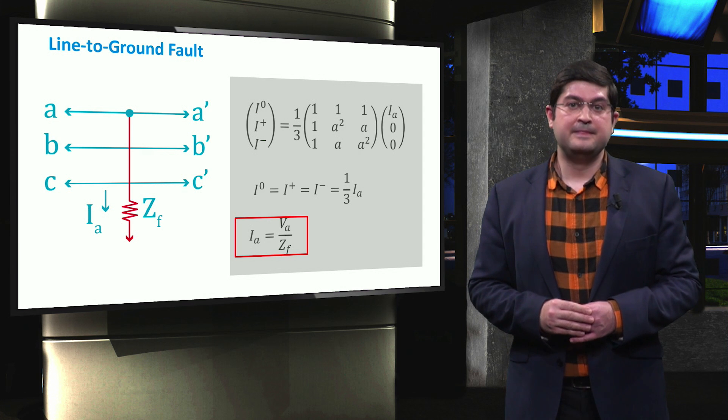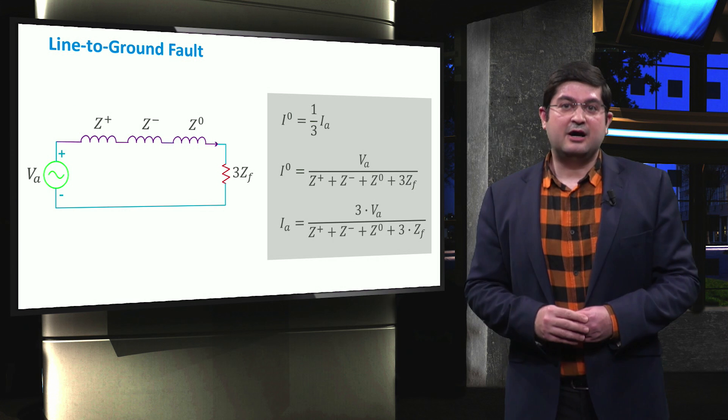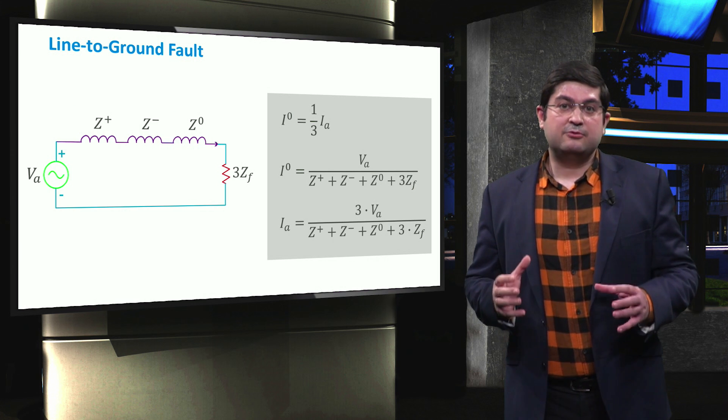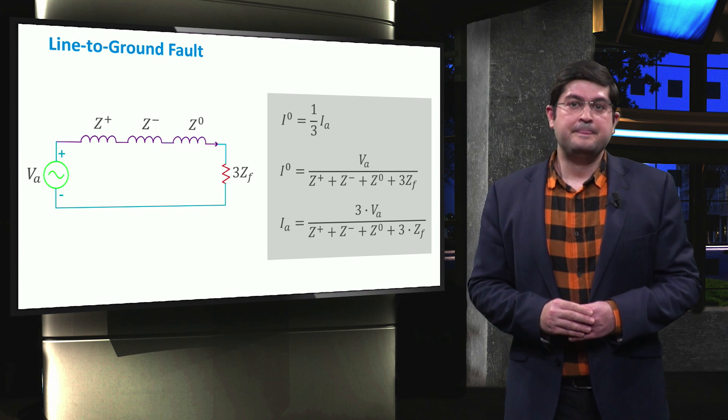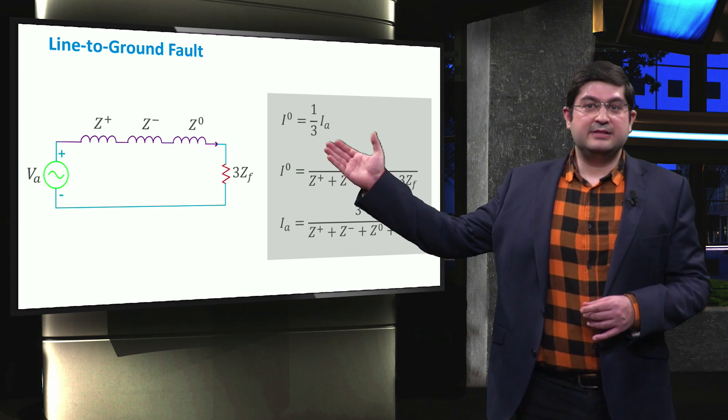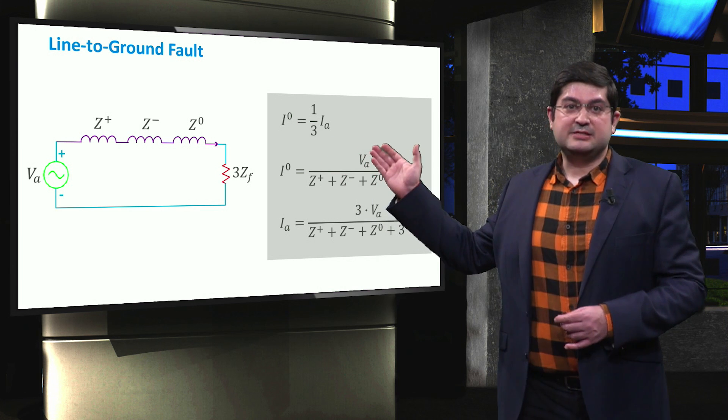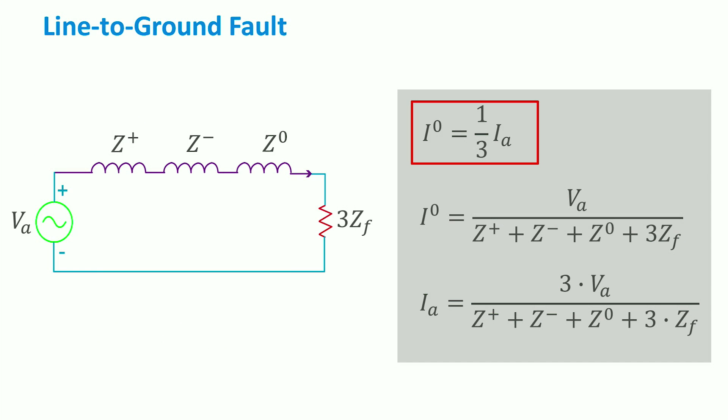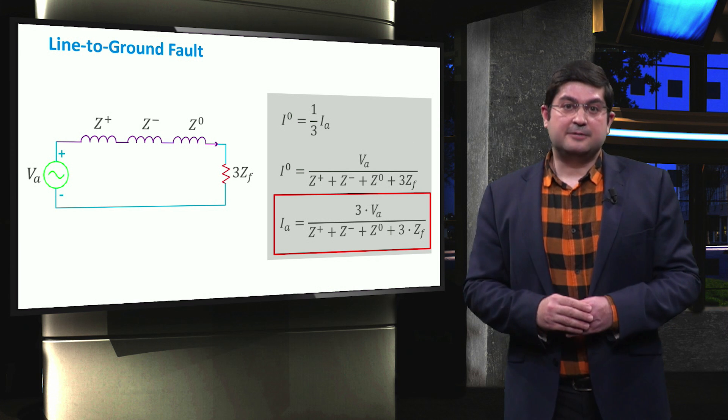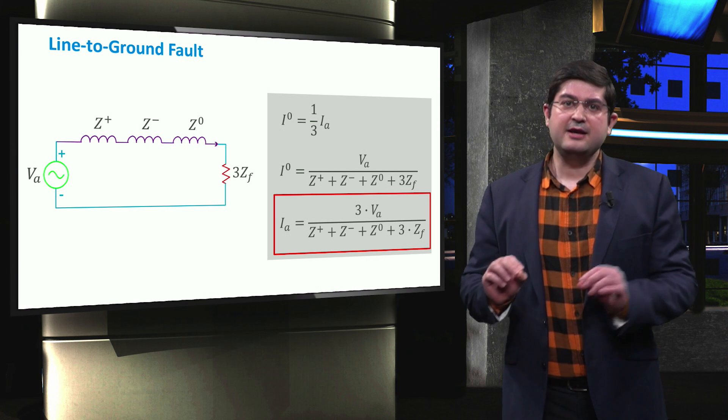In this slide, we show how the inclusion of the line impedance makes the previous calculation more accurate for a line-to-ground fault. We represent the impedances by the positive sequence impedance, negative sequence impedance, and the zero sequence impedance. As we have obtained, the zero sequence current equal to one-third of the fault current in the equivalent circuit, the three times ZF appears. The zero sequence current can then be obtained dividing the voltage of phase A by the sum of the impedances Z plus, Z minus, Z zero, and the three times of ZF. Finally, the fault current is obtained depending on the value of both line and fault impedances.